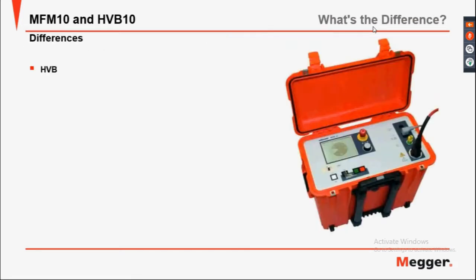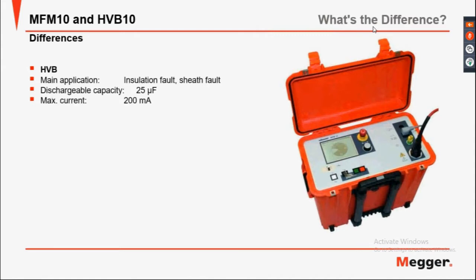So what are the differences? For the HVB, the main application is insulation fault and sheath fault, with a dischargeable capacity of up to 25 µF. The maximum current is 200 mA. The minimal measurable voltage is 5 µV.